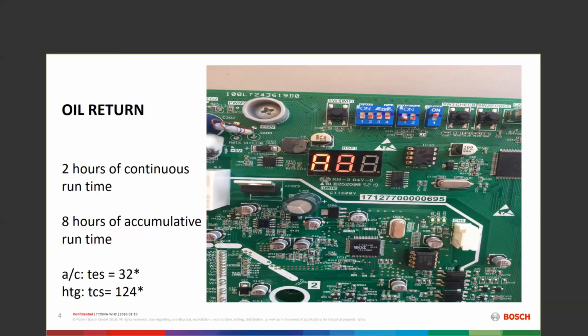So 2 hours of continuous time, 8 hours of accumulative time. So if for some reason I haven't what we would call ramped up during that 8 hours of cumulative time, I will go into oil return. So we think that you're going to see more oil return scenarios when you get out there and open up the cover of the unit on the 2.0 than you saw on the 1.0.